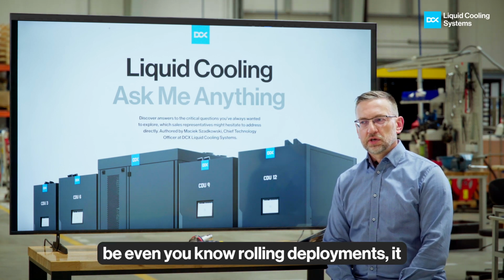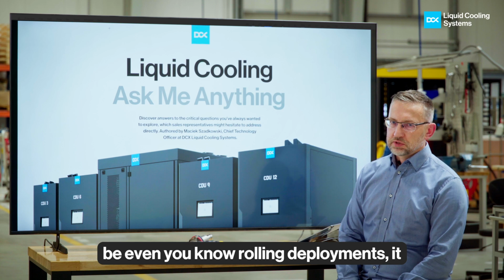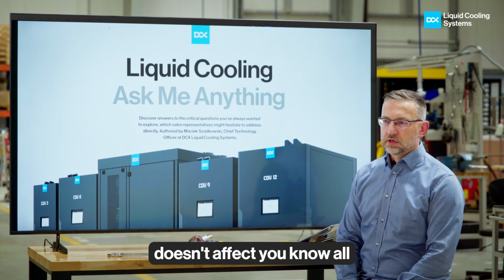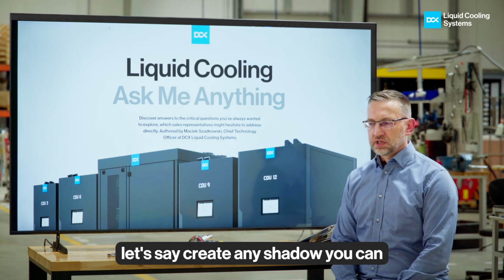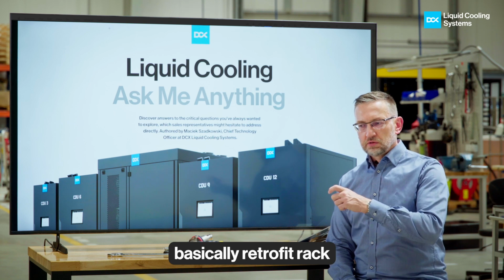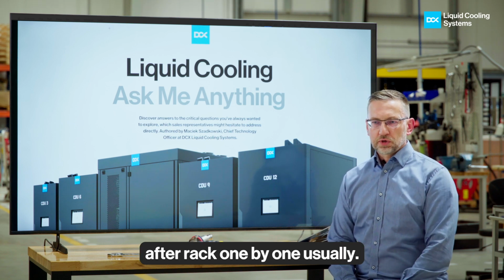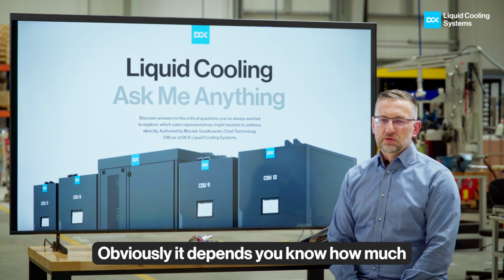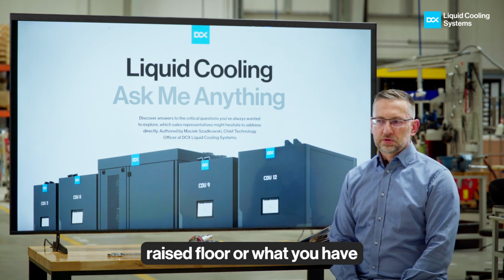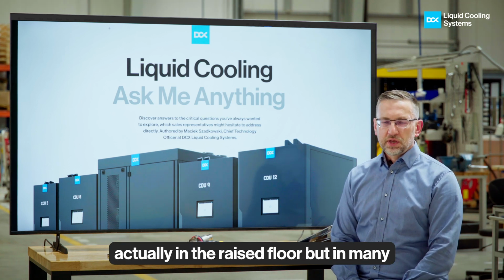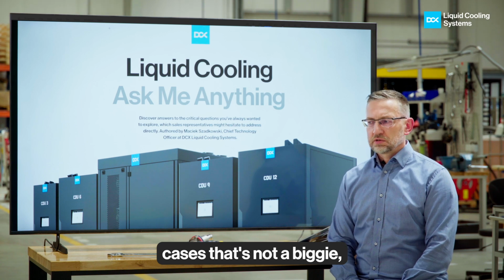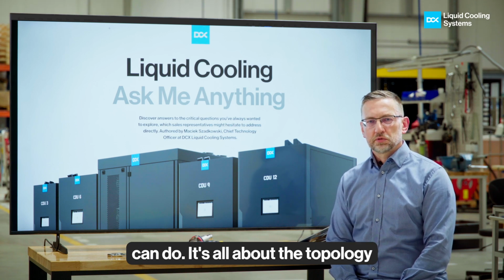In general, you can basically seamlessly retrofit your existing data hall, adding those liquid cooling components without touching the rest. It could even be a rolling deployment. It doesn't affect all the racks - you don't have to create any shutdown. You can basically retrofit rack after rack, one by one, usually. Obviously it depends how much space you have in the raised floor, and what you have in there. But in many cases that's not a biggie. That's something you can do.